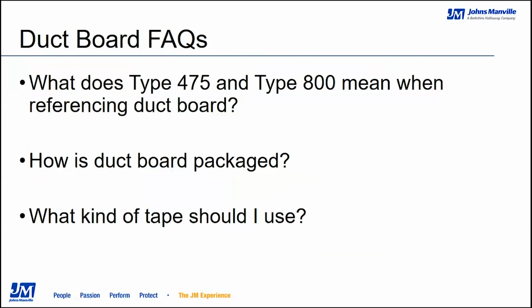The tape and closure system is extremely important, an integral part of the fiberglass duct construction process. There are a couple closures that comply with UL 181: a pressure-sensitive tape, which you saw him squeegeeing down, a heat-activated aluminum tape, and a glass fabric and mastic. All of those have been tested, and you can get them at your local HVAC supply house or distributor. Make sure you do not use regular duct tape - that will not work. You have to use a UL 181 approved tape to make sure the system stays closed and sealed.